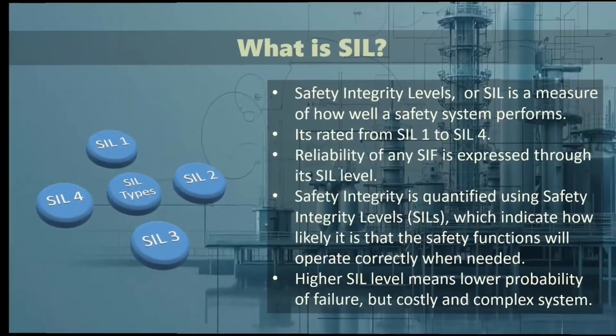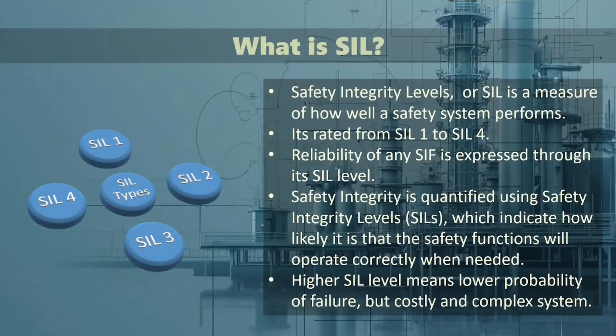Now, on to the main event: safety integrity levels, or SIL. It is a measure of how well a safety system performs, rated from SIL 1 to SIL 4. The higher the SIL, the lower the probability of failure, but also the more complex and costly the system.